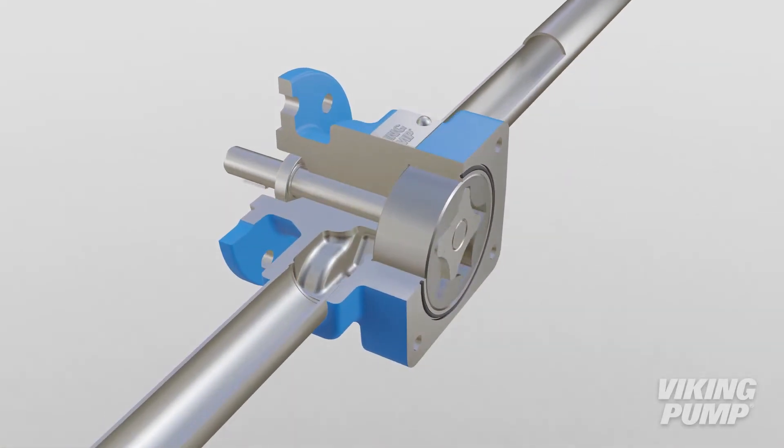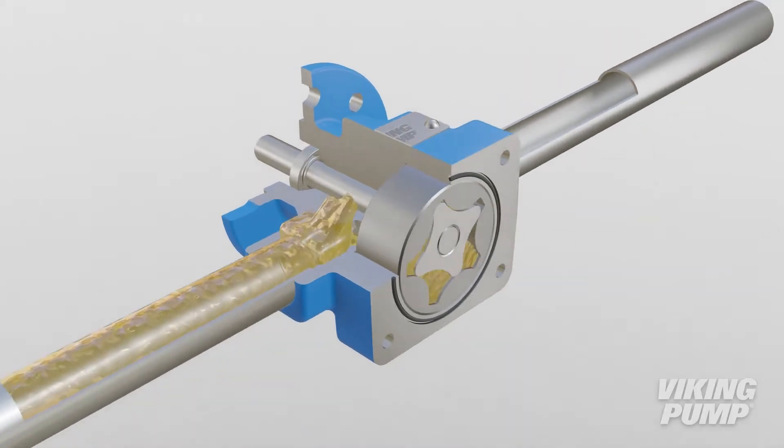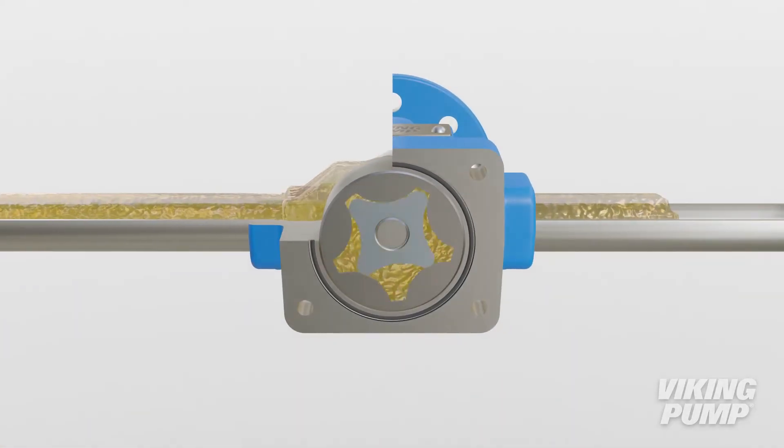Liquid enters the suction port between the teeth of the elements. There is a smaller inner driver element and a larger outer driven element. While tooth counts vary, the outer element has one more tooth than the inner element, creating cavities between the teeth.